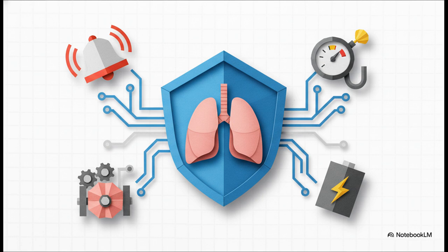If the oxygen supply suddenly fails, a loud alarm screams immediately. If the airway pressure spikes too high, a physical relief valve pops open to protect the lungs. If the patient stops breathing unexpectedly, an apnea failsafe automatically triggers mechanical backup breaths. And if the entire hospital loses power, built-in backup batteries instantly take over. Preserving the safe delivery of oxygen is, without question, the ultimate prime directive here.